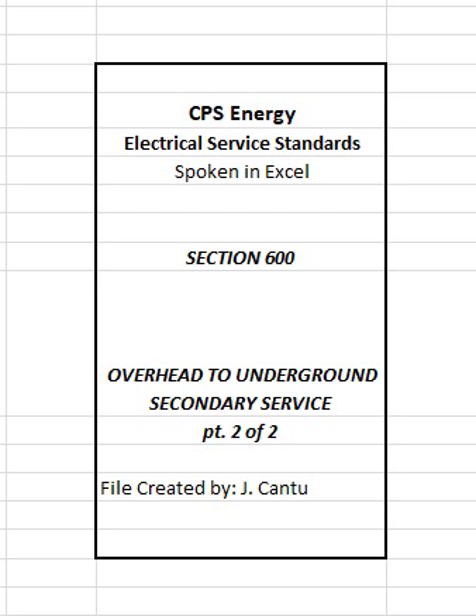606(2) Identification. Customer shall clearly and permanently identify the grounded, neutral conductor, S, of the service entrance conductors before CPS Energy connects the service lateral, refer to Section 400. 607 Metering. All metering equipment shall be installed on the exterior of building or structure at a location approved by the CPS Energy Customer Service Representative and in accordance with Section 1800.